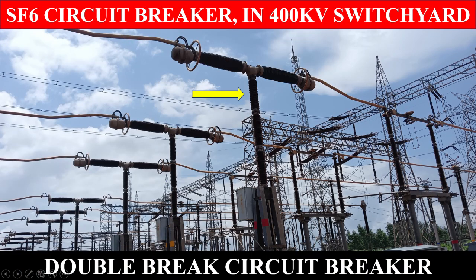Disadvantages. 1. SF6 breakers are costly due to the high cost of SF6. 2. Since SF6 gas has to be reconditioned after every operation of the breaker, additional equipment is required for this purpose.